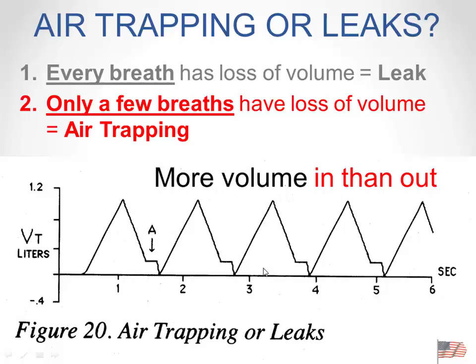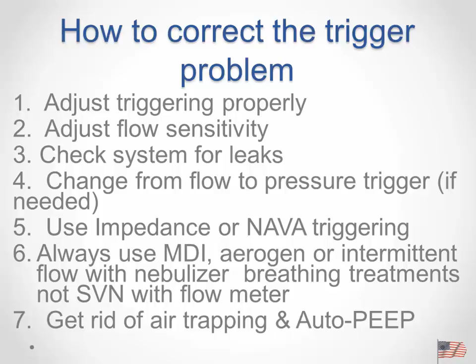How to correct the triggering? Well, make sure the sensitivity is set correctly. Check for leaks within the system, change from flow to pressure triggering if needed, and use some other type of triggering if it's available. And if you're using something where I'm adding flow to the circuitry, stop doing that and use an MDI or an Aerogen, and then get rid of air trapping and auto-PEEP.